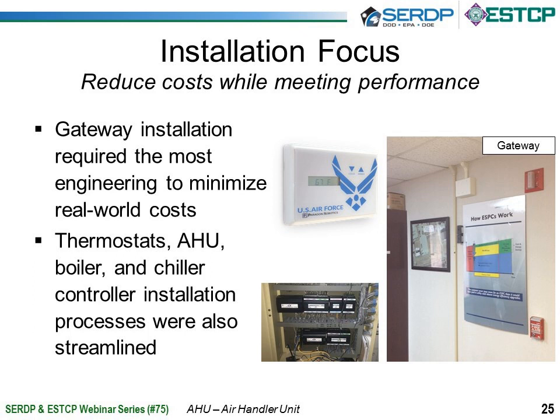So I'll briefly step through the installation here. There were really two stages to the installation. For the first half, we wanted to make sure the retrofit controls met all the design algorithms that we'd set out, and tuned them to make sure that we got the energy savings correct. The second half, which was arguably a little bit more important, was to look at reducing the overall installed cost of this entire system. Because we're really targeting a return on investment number, not only do we need to save energy, but we also need to get the installed cost low.